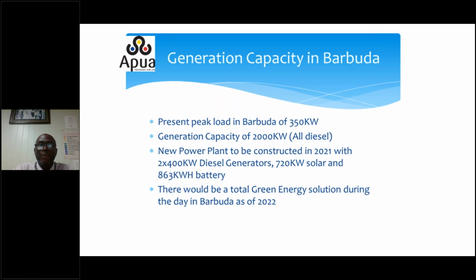And Barbuda, we would not want to forget Barbuda, our sister island, very small, with only a peak demand of 350 kilowatt. We have quite a bit of generation capacity, 2,000 kilowatt or 2 megawatt, all diesel. But through efforts and with assistance from the UAE, we are going to be relocating the power plant in Barbuda from where it's presently located. Anytime there's a storm, you have water ingress into the power plant. So we will be putting it in a more resilient and secure area. Also, we'll be adding 720 kilowatt of solar and 863 kilowatt-hours of batteries.